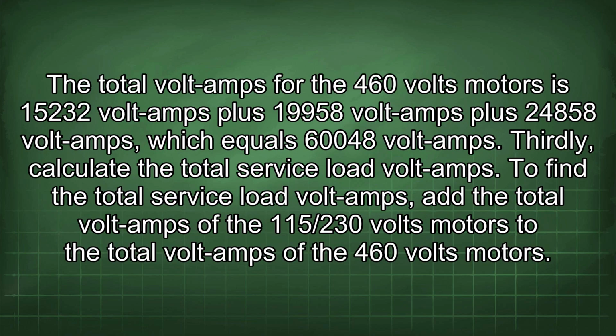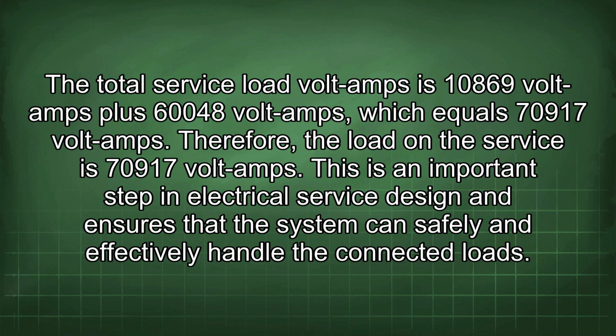Next, add up the volt amps for all the 460 volts motors. The total volt amps for the 460 volts motors is 15,232 volt amps plus 19,958 volt amps plus 24,858 volt amps, which equals 60,048 volt amps. Thirdly, calculate the total service load volt amps. To find the total service load volt amps, add the total volt amps of the 115/230 volts motors to the total volt amps of the 460 volts motors. The total service load volt amps is 10,869 volt amps plus 60,048 volt amps, which equals 70,917 volt amps. Therefore, the load on the service is 70,917 volt amps. This is an important step in electrical service design and ensures that the system can safely and effectively handle the connected loads.